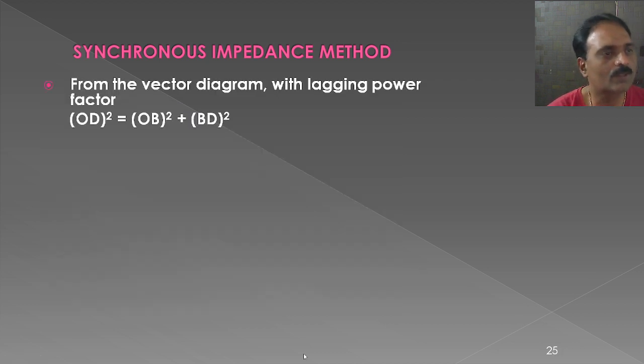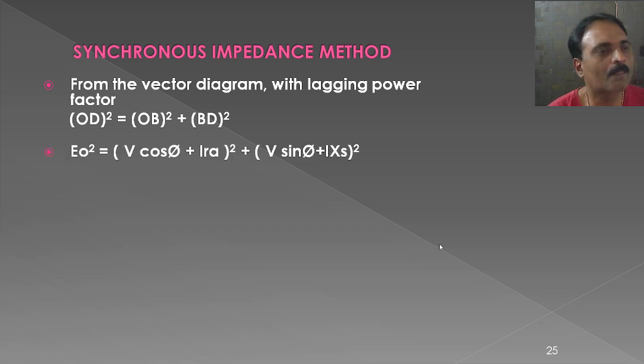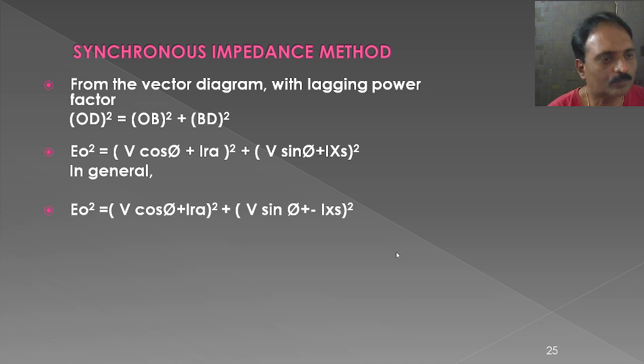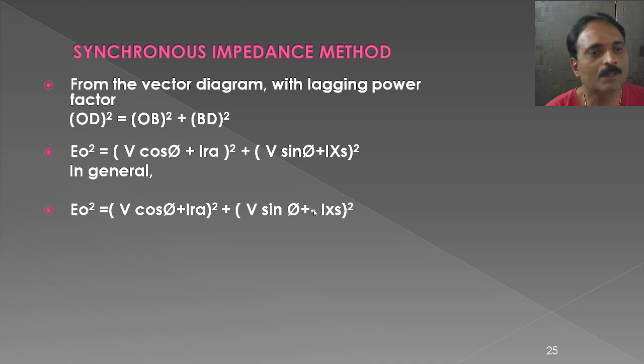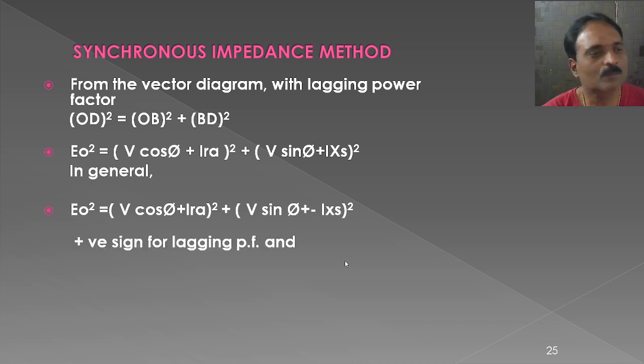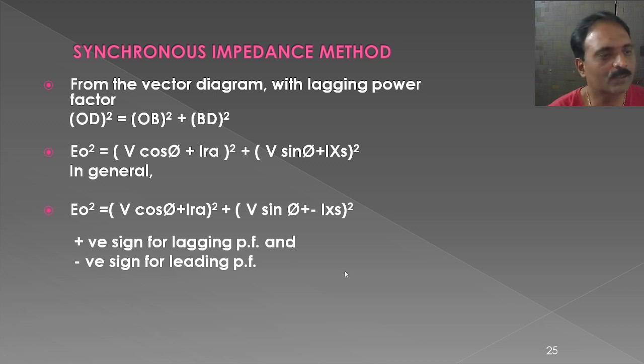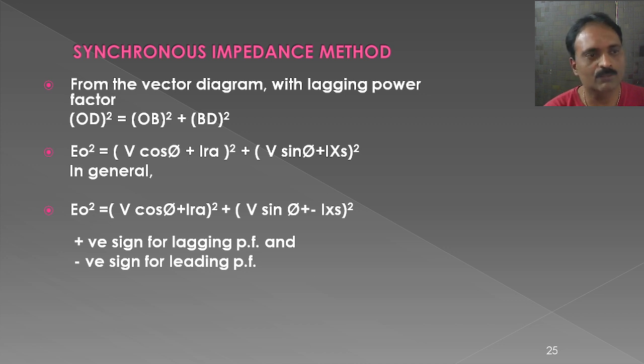This formula is for inductive load, where we use a plus sign: E0 = √[(V×cos(phi) + I×RA)² + (V×sin(phi) + I×XS)²]. For capacitive load, we use a minus sign: the second term becomes (V×sin(phi) − I×XS)². In general, the positive sign is for lagging power factor and the negative sign is for leading power factor. From this formula, we find E0, then calculate regulation as (E0 − V) / V × 100. This is how we find regulation using the synchronous impedance method.